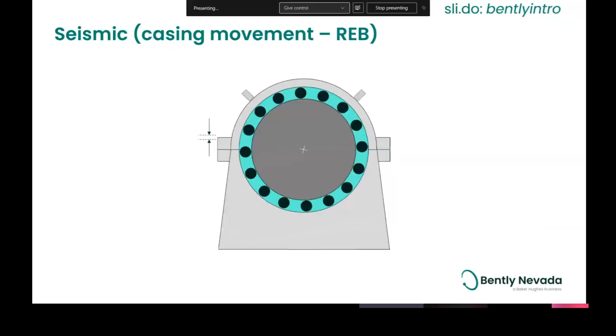So if there is a fault on the outer race, as an example, as each of those rolling elements goes by, the accelerometer is going to pick up that frequency as it goes ping, ping, ping going by there. And even more so, if you think of even higher frequency, if you think of each of those little rolling elements going past that defect as a tiny little hammer hammering that housing, you can almost imagine a little ping noise going out, ping, ping, ping, and that high frequency noise is going to show up very early in defect life. And accelerometers can pick up that very high frequency, and with the right sort of measurement and the right sort of processing in a monitor, we refer to it as enveloping, there's other terms for it, you can pick up those very high frequencies and get very early indication of bearing health degradation. So that's why accelerometers are very useful.